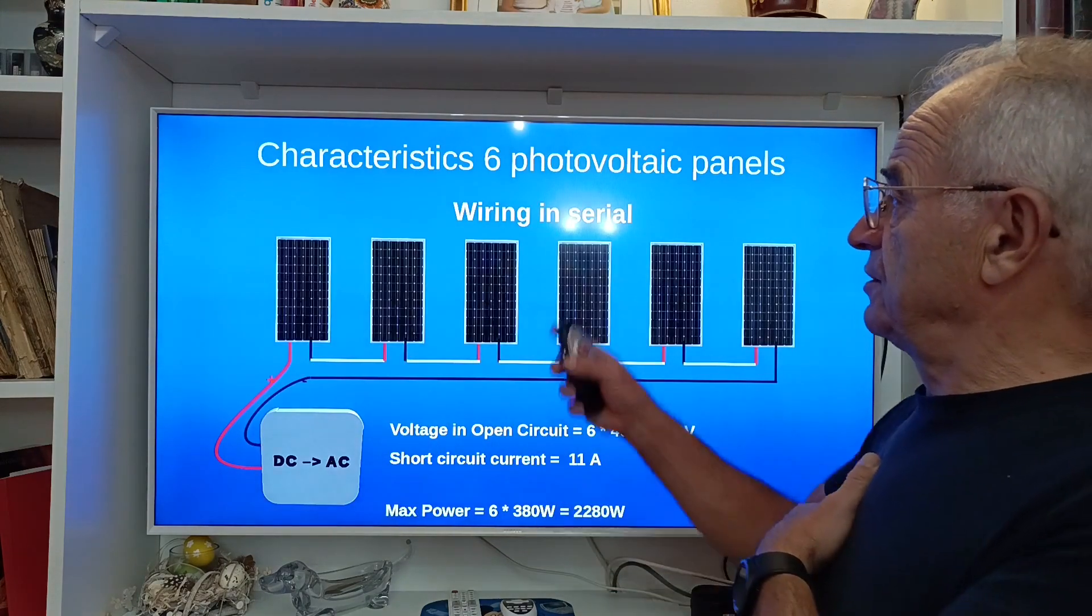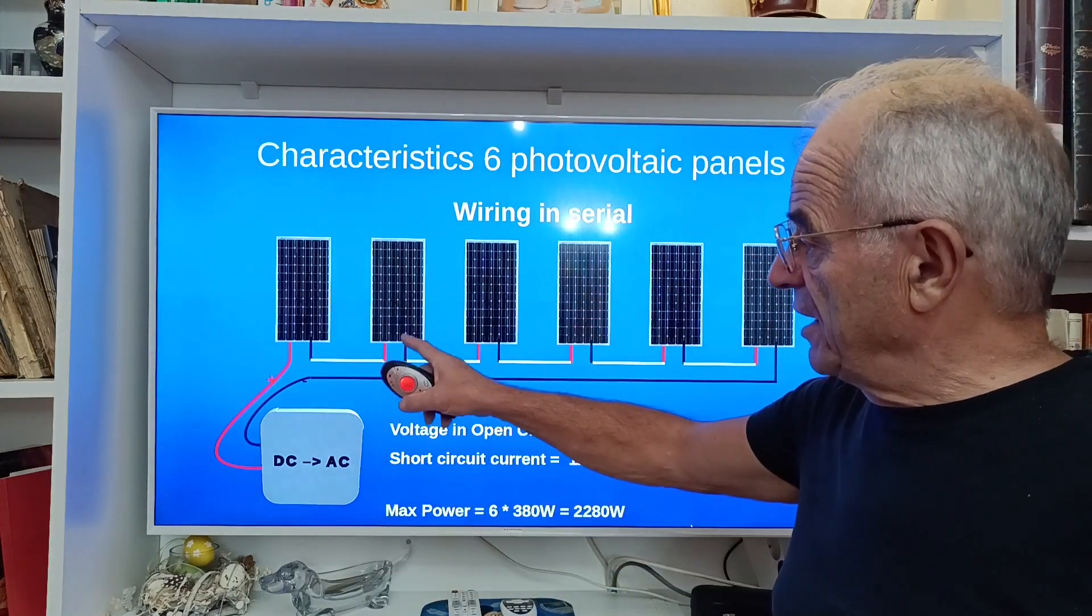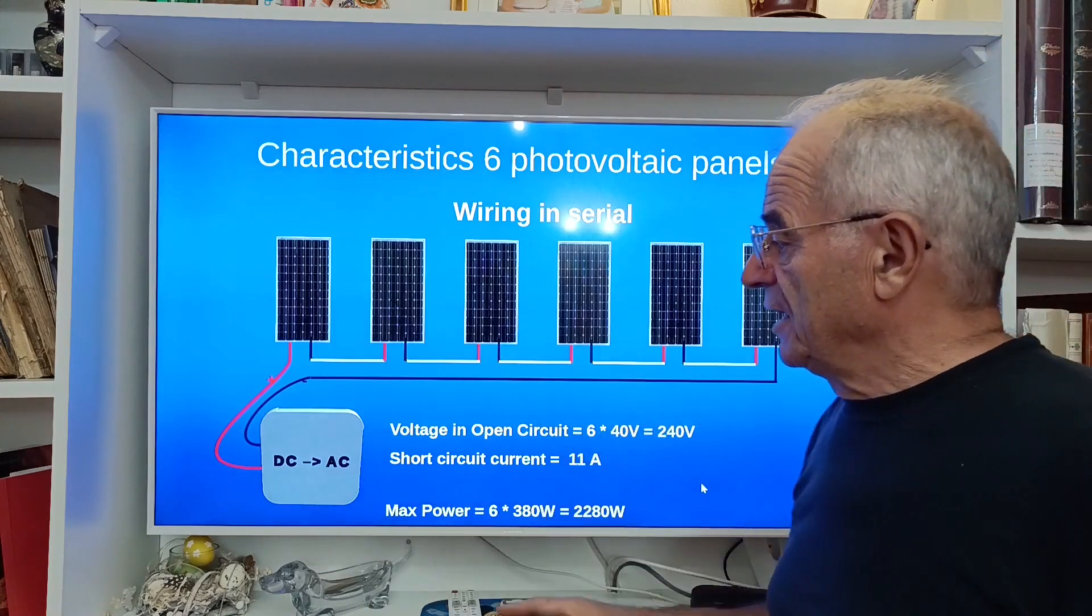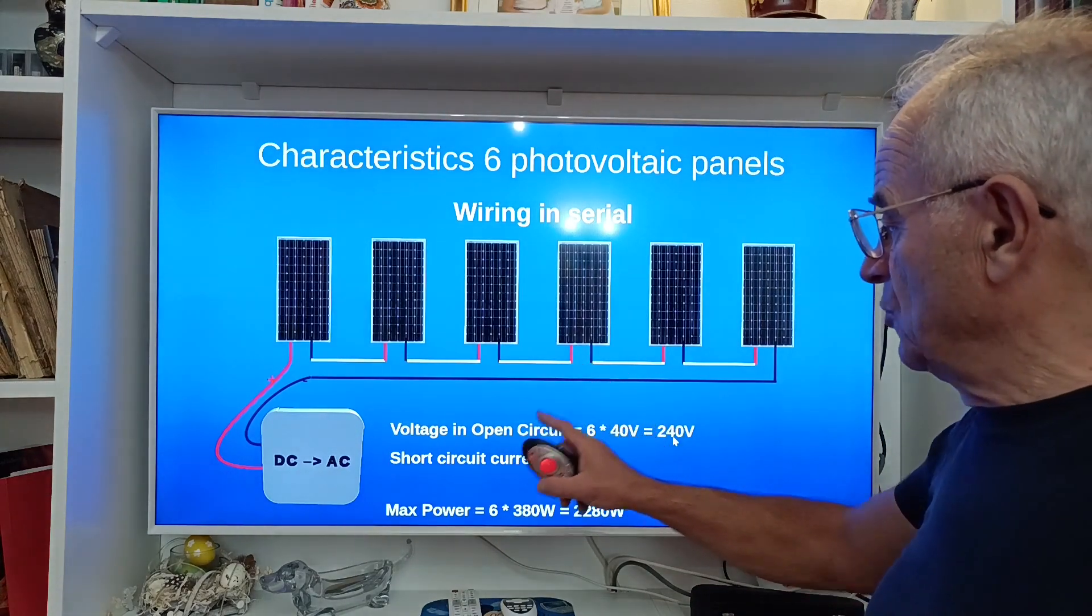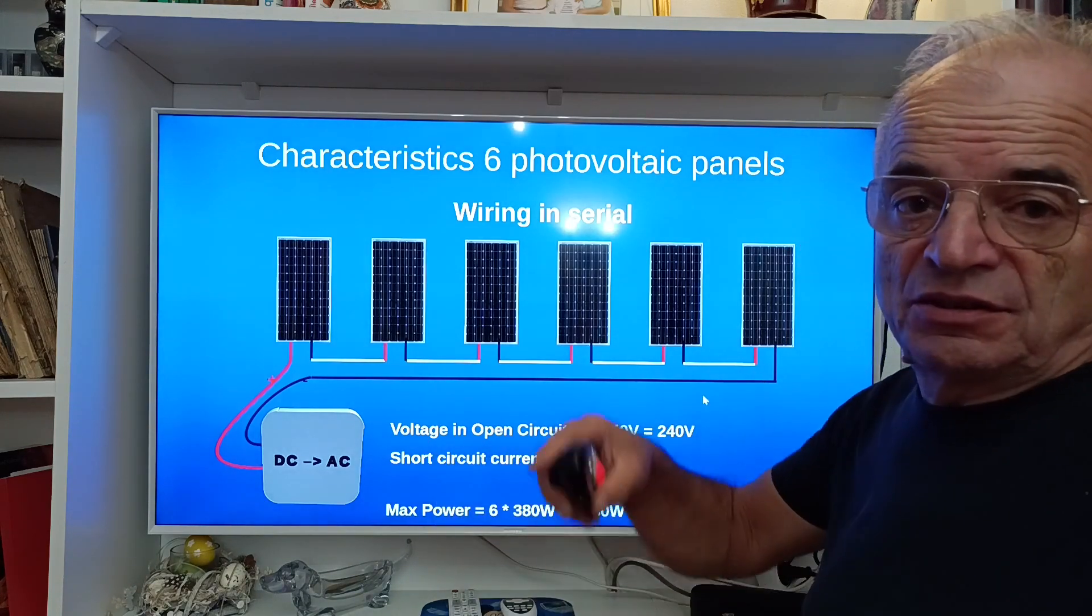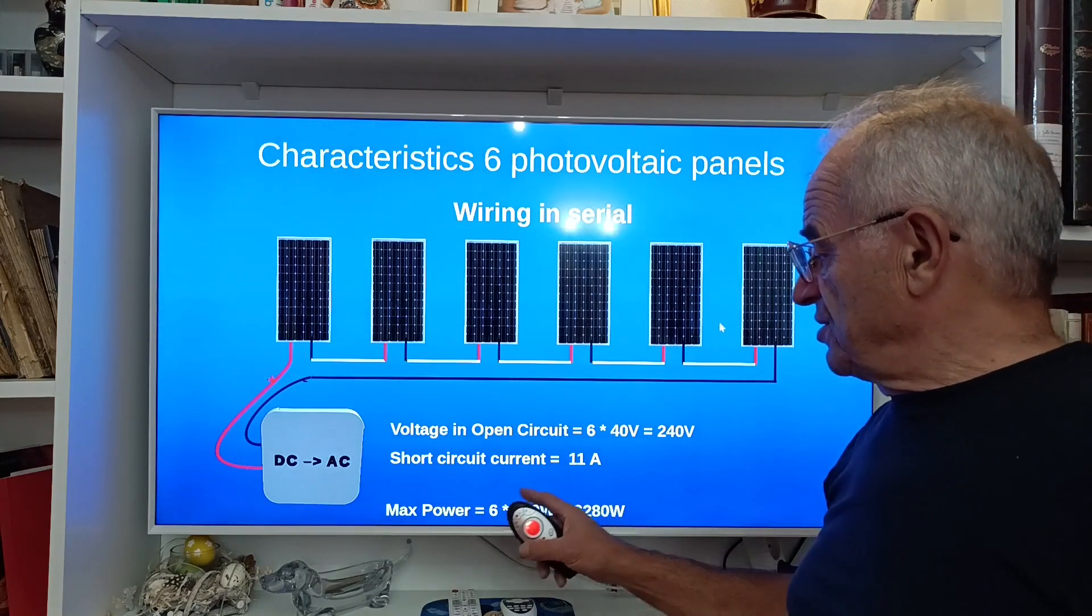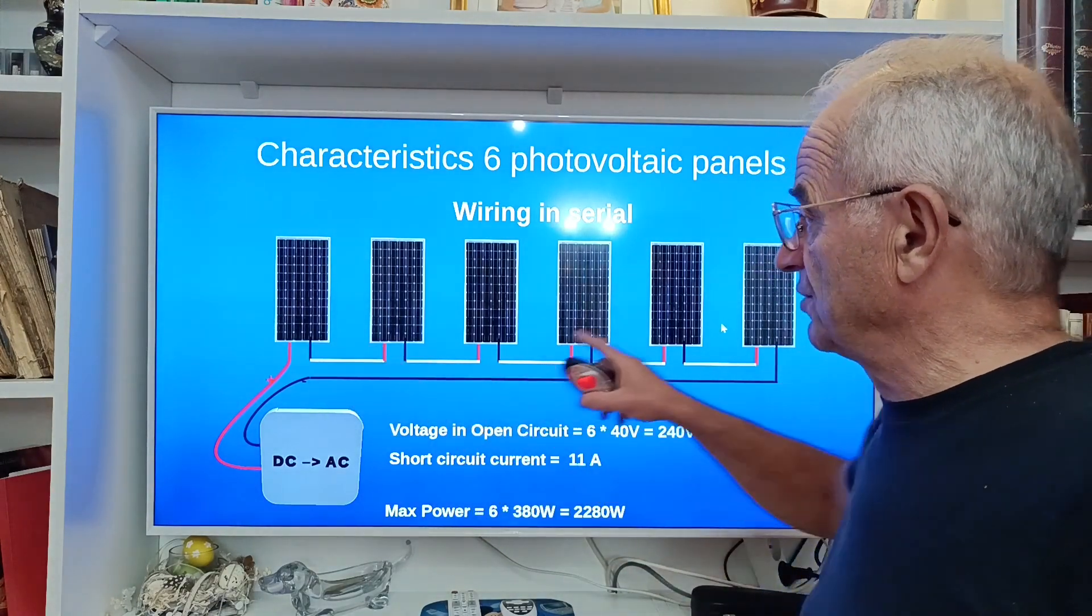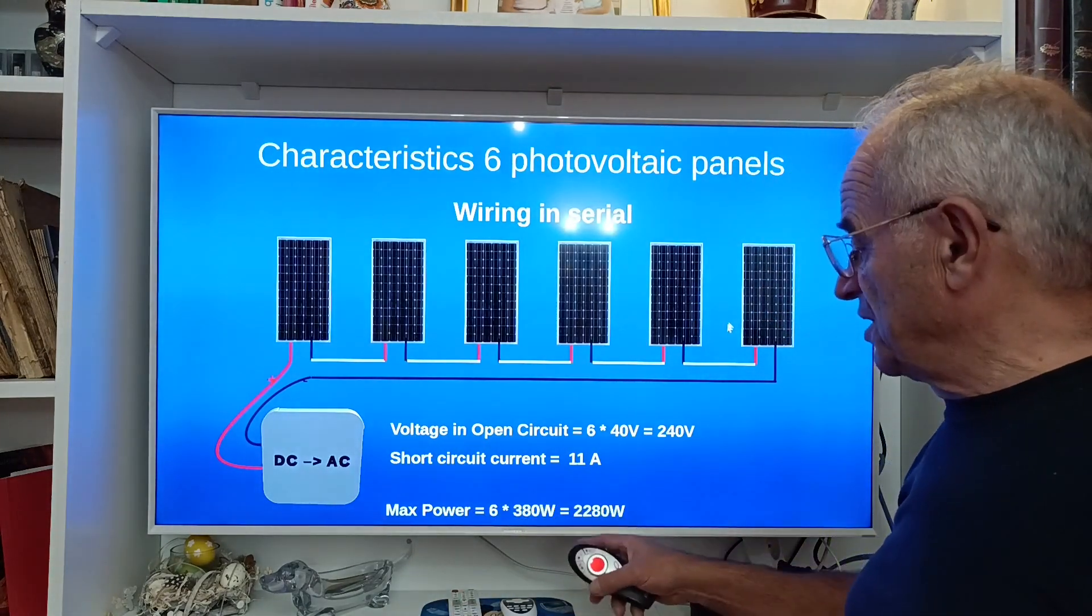Another way to connect all six panels is to wire them in serial, so we connect the minus of one panel to the positive point of the other and so on, all in serial, and we connect to the DC to AC converter. In open circuit we'll have six times 40 volts because in that case you add the different voltages of these six panels, so we obtain 240 volts. In short circuit we have 11 amps, the current of one panel, because they are all in serial.